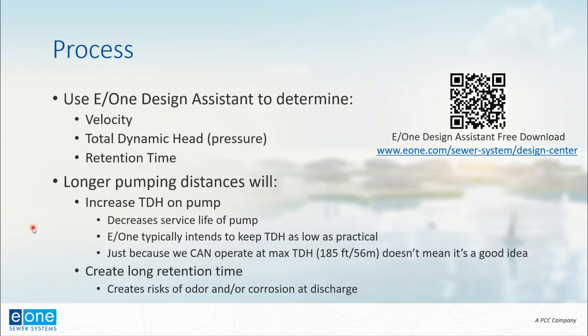Now that we know the concept and what we're trying to solve, how do we do it? We can do calculations by hand, or use the E/One Design Assistant to determine feasibility. Using the Design Assistant, we'll determine the velocity in the pipeline and understand the total dynamic head — that's one of the key things. Essentially, we need to determine whether pumping through a pipe of a given size, length, and elevation gain requires less than the pump's capability. If the system total dynamic head is less than 185 feet, an E/One pump will work in that application.